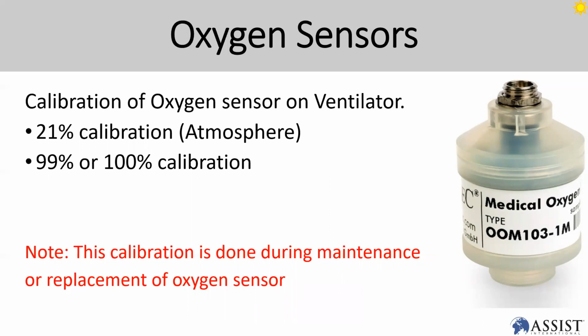If the calibration passes, that means the sensor is still good. Because always remember the oxygen sensor has a lifespan, maybe 18 months, sometimes 2 years, depending on the usage, but that's the maximum. Some of them, at 18 months, you need to replace because the performance changes.